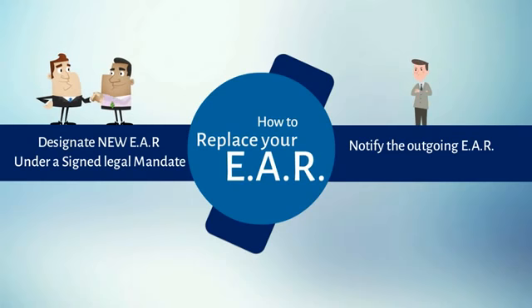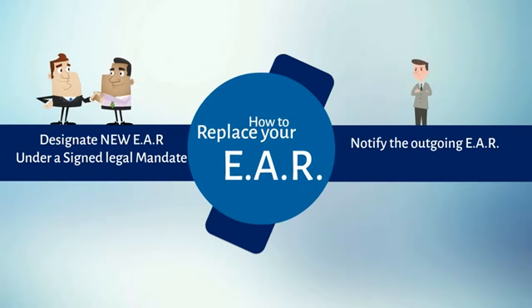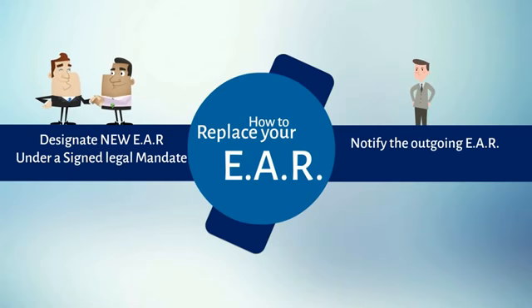2. The outgoing EAR needs to be notified by the manufacturer that from this day forth the new EAR will take over. In case of class 2A, 2B, or 3 medical devices, the notified body needs to be notified of this change. And in the case of class 1 medical devices, the EU authorities need to be notified of this change.